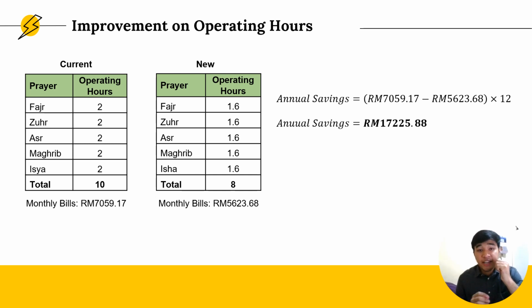The monthly bill on the current operating air conditioning is 7,059 ringgit per month. And after we reduce the operating hours from 10 hours to 8 hours, the monthly bill reduces to 5,620 ringgit. So we will subtract the value of the current and the new improvement and multiply by 12 months to get the annual savings. So we will get the annual savings of 17,225 ringgit.